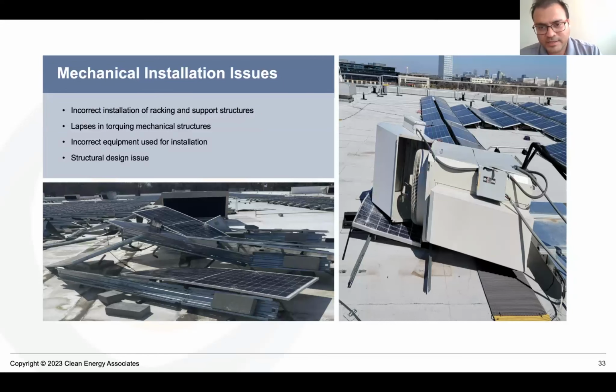We had a site that was just missing a screw over the enclosure, due to poor workmanship. These are some examples of mechanical installation issues. I inspected this site earlier this year, shown on the left, and we reported some major issues regarding the racking: anchor points missing, and ballast blocks not placed as per the design recommendations from the EOR or structural engineer.